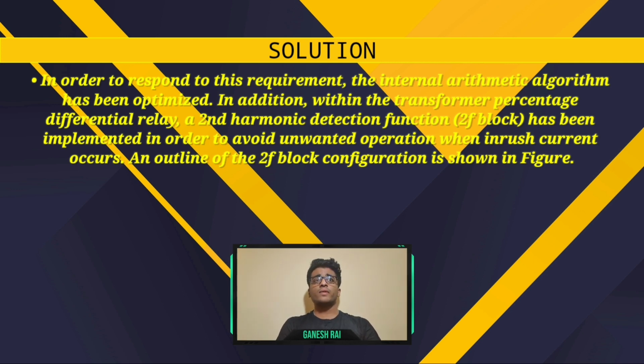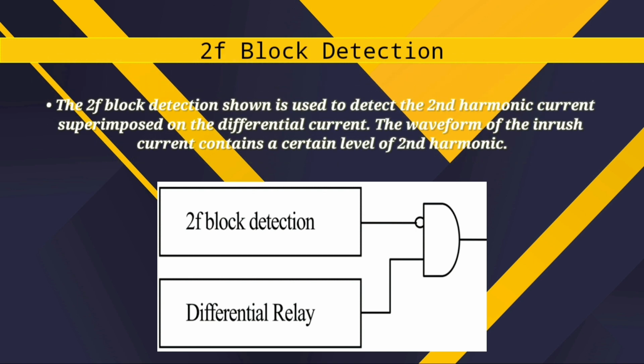In addition, within the transformer percentage differential relay, a second harmonic detection function named the 2F block has been implemented in order to avoid unwanted operation when inrush current occurs. An outline of the 2F block configuration is as shown in the figure. The 2F block detection is used to detect the second harmonic current superimposed on the differential current. The waveform of the inrush current contains a certain level of second harmonic.